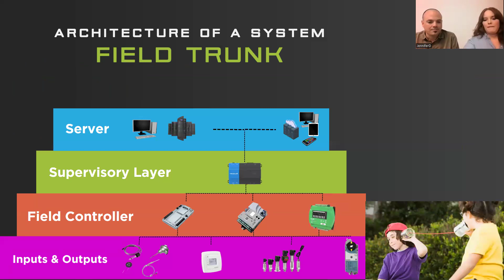Well, they have to communicate somehow, and that's through either wired or wireless communication. These are three of the main methods you're going to see in order to reach those goals. The first is master slave token passing, or MSTP. This is a very standard style of wiring within the controls industry, mainly because it is a two conductor and it is daisy chained. So it's very simple to install on a device. As you can see in the image, it goes from one to the next to the next. There is no intercommunication. It's daisy chained.